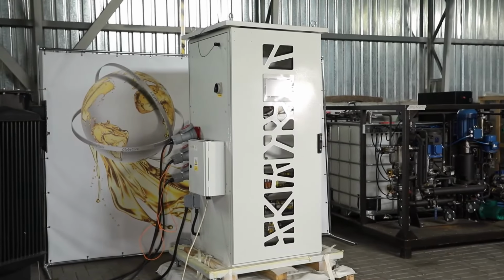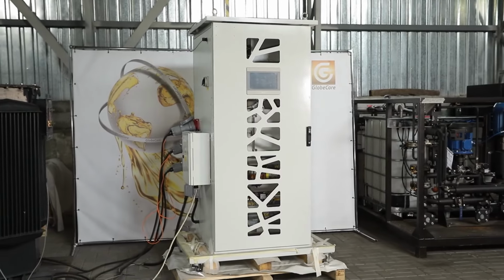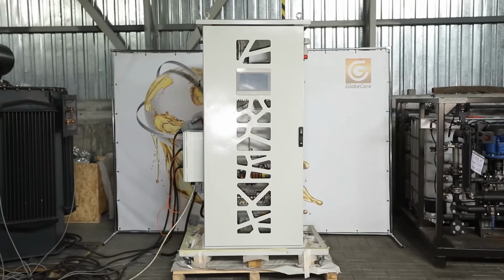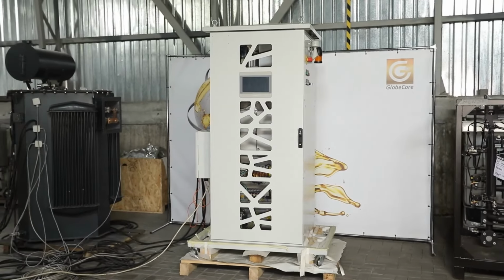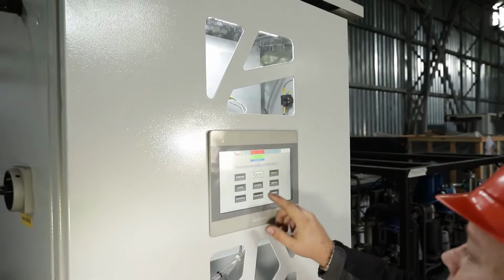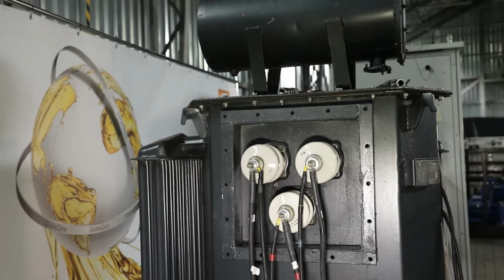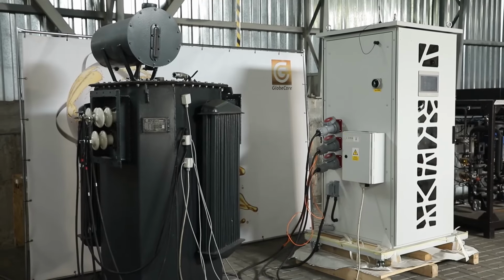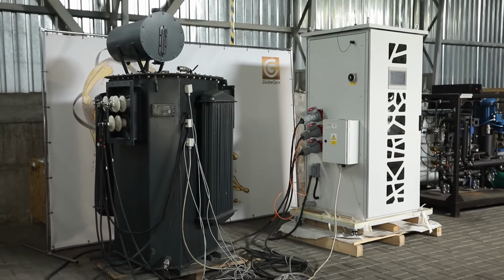The low-frequency heating method can be used to dry the windings of new or functioning transformers of any size in repair shops and in the field. High-quality drying using low-frequency heating increases the electrical strength and extends the life of the transformer's solid insulation by at least 10 years and most often more.